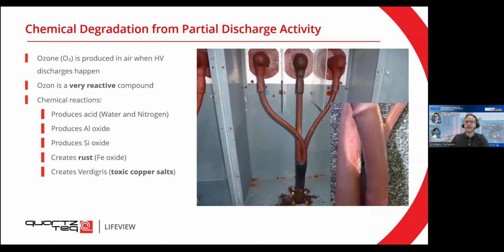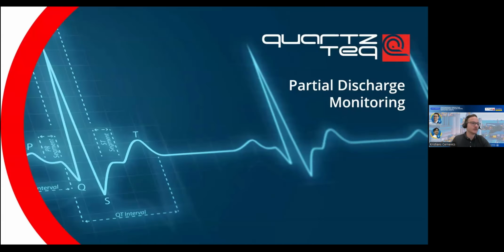For those who have a bit of chemical background, essentially how this degradation happens is that once the PD happens, there's a high electrical voltage discharge in the air. Air contains oxygen molecules, and with this additional charge, actually ozone is made. Ozone is a radical that is very, very reactive. So if ozone touches something else, a chemical reaction will happen. It can produce acid from water and nitrogen available in the air. It can produce aluminum oxides, silicon oxides, iron oxides to create rust. All these compounds are in the machines or around the machines. So you're going to see these types of chemical reactions happening, and then degradation of your material. And if you have copper parts, you can even have toxic copper salt made from ozone interacting with copper. So I hope I convinced you that partial discharges are important to monitor.